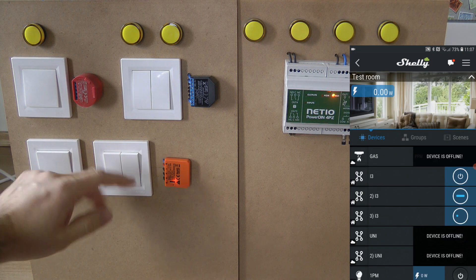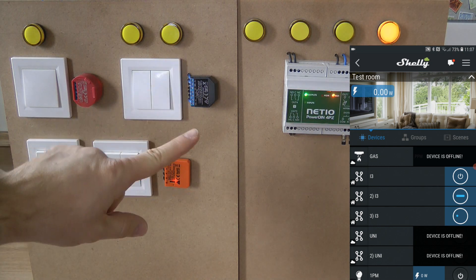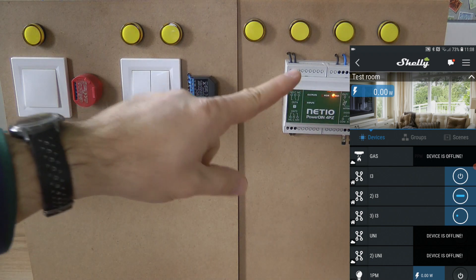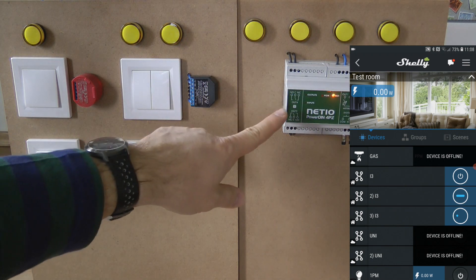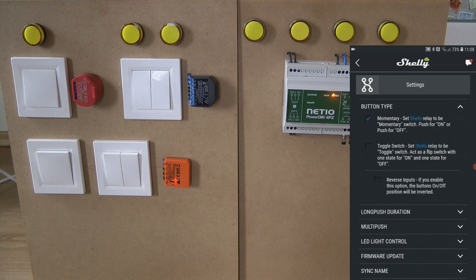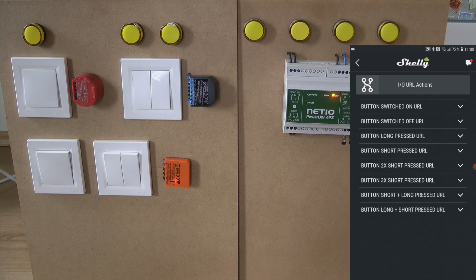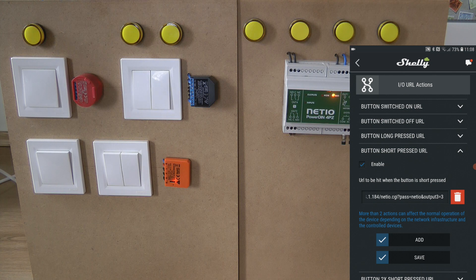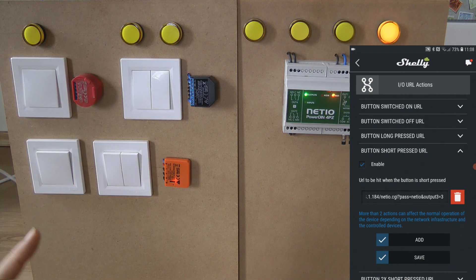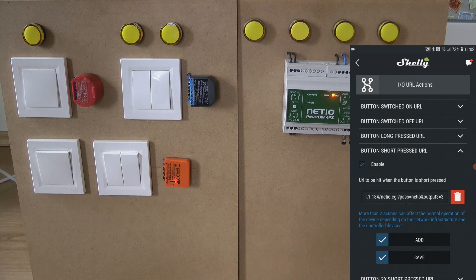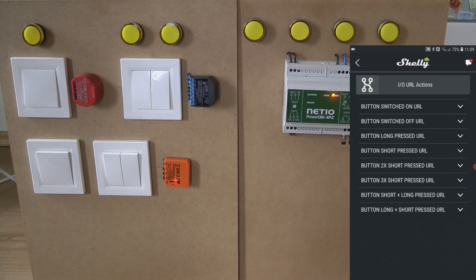For the third button, also configured as a momentary button, pressing it turns the third output on momentarily using the PowerDin's built-in auto-off feature. In the settings, the button type is set to momentary, and in the short press URL action, the URL ends with output three equals three — three being the momentary on action. When triggered, it turns on and then automatically turns off after the default off time, which is approximately 2200 milliseconds, just over two seconds.